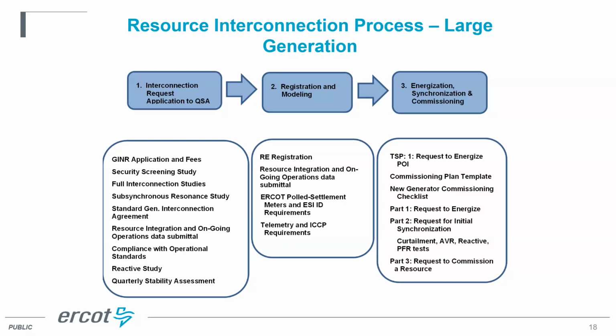We also have to make sure they comply with our operational standards. One of which is they do a reactive study to make sure their design will meet our reactive requirements, 0.95 lead and lag at the point of interconnection. Next is the quarterly stability assessment, which I'll go into a little bit more on the next slide.